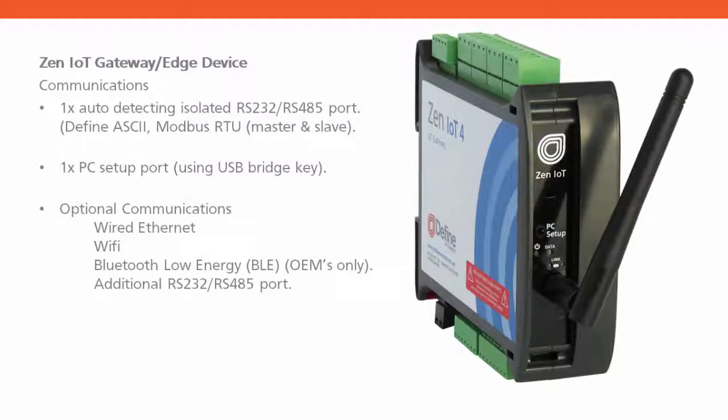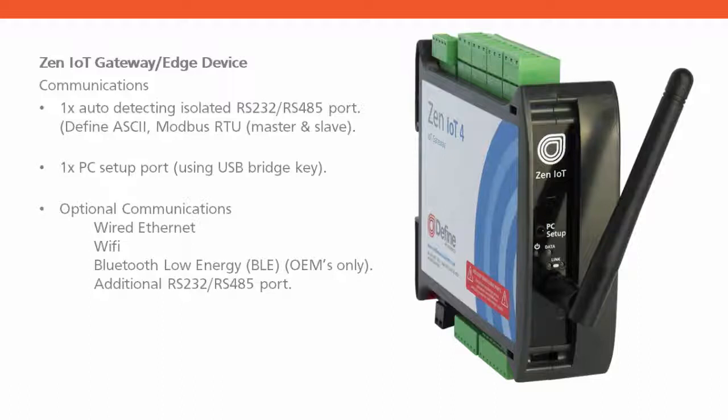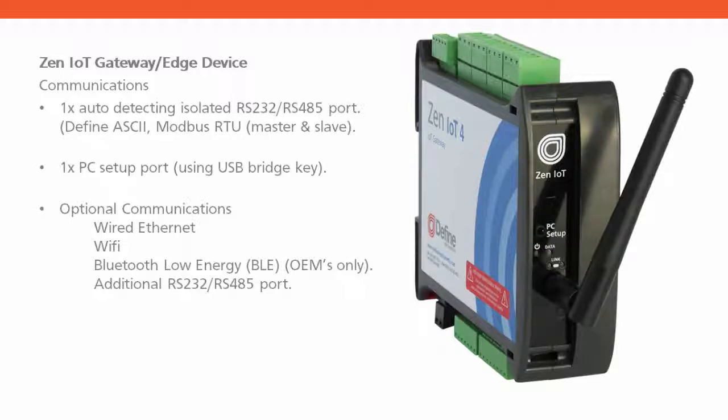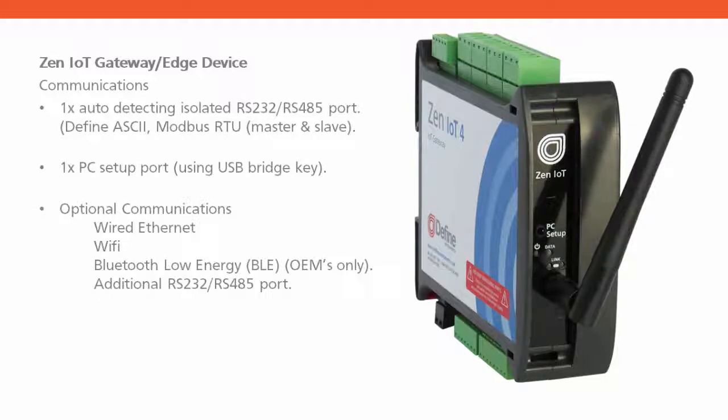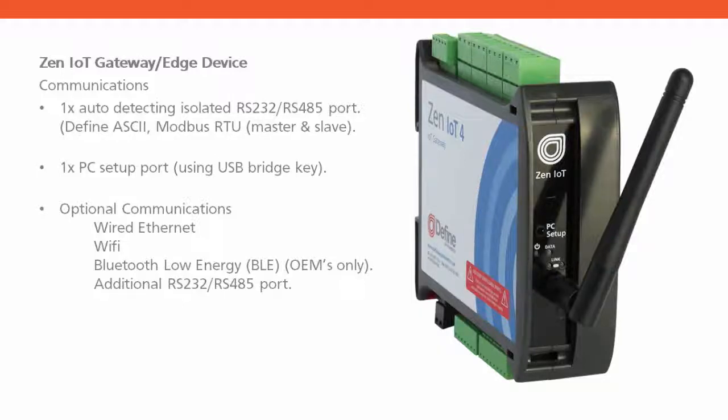The Zen IoT Gateway also has several communications options. It has a fully isolated RS-232-485 port which is auto-detecting. It also has a programming port on the front to make it easy to configure the Zen IoT Gateway through our Workbench programming tools with our USB bridge key. It also has optional communications, either a wired Ethernet port, Wi-Fi as shown in the image, or low-energy Bluetooth, and an additional RS-232-RS-485 port for driving an external modem.